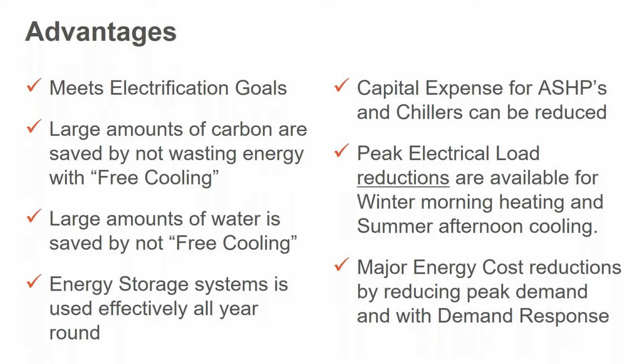So to summarize, the system will meet the electrification goals of the city. Large amounts of carbon can be saved by not wasting that energy through free cooling. You're saving it for tomorrow morning's warm up. There's large amounts of water that's not being evaporated off. So in green buildings, that's a lot of water that you're not wasting with free cooling because you're not running that cooling tower. We have an energy storage system being used effectively the entire year. So that capital expense is used well. The capital expense for the air source heat pumps and chillers can be reduced because you've got a thermal storage system in there that can help you design for the average load instead of the peak. And you can have the exact same redundancies and safety factors as you do in any other design. Tell us what you need for that, we can give it to you.